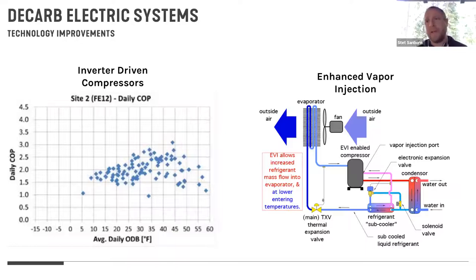And that's really important both from a cost of energy to heat standpoint, but also being able to match load, so we don't necessarily have to buy as much heat pump. The other big benefit that we see for heat pump systems in cold climates is one that is relatively new, and it's looking at using enhanced vapor injection.